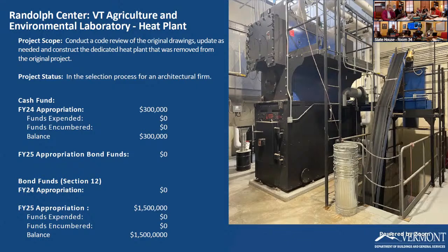During the design, I don't think it was caught that the colleges do not run their heat plant at 60 PSI. The autoclaves inside the lab require a minimum of 50, so they've been giving us up to 48. It has been working, but there are other problems - it's not a constant 48 PSI that they're giving us. Sometimes it drops down to 20.